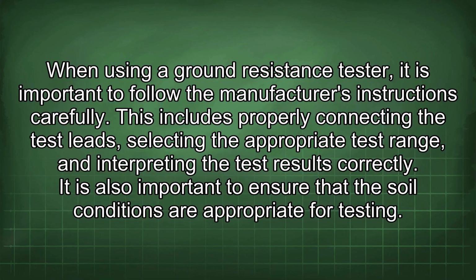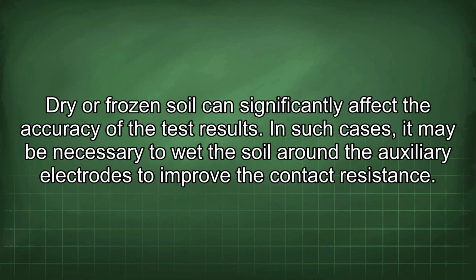When using a ground resistance tester, it is important to follow the manufacturer's instructions carefully. This includes properly connecting the test leads, selecting the appropriate test range, and interpreting the test results correctly. It is also important to ensure that the soil conditions are appropriate for testing. Dry or frozen soil can significantly affect the accuracy of the test results. In such cases, it may be necessary to wet the soil around the auxiliary electrodes to improve the contact resistance.